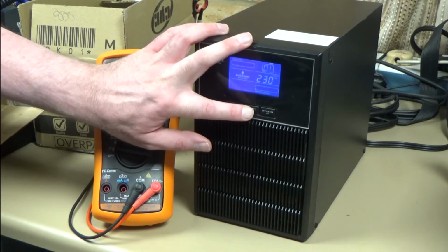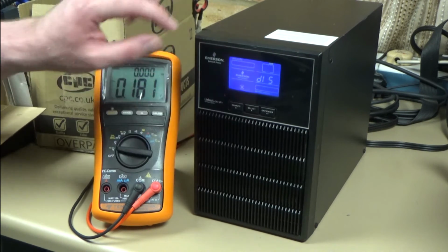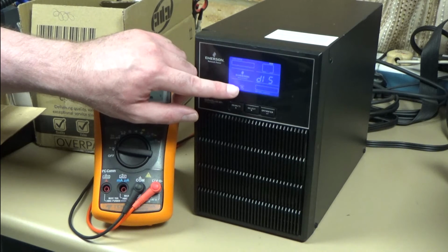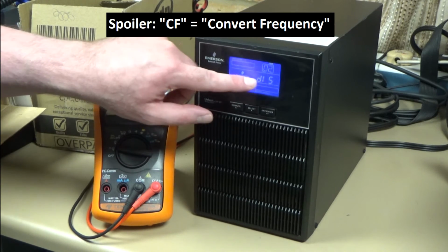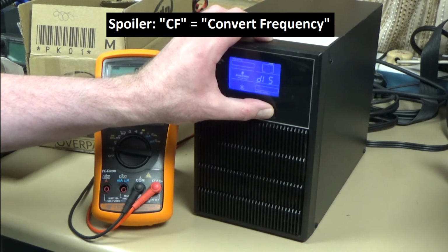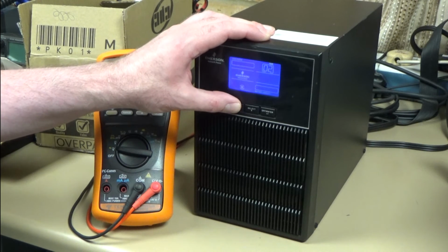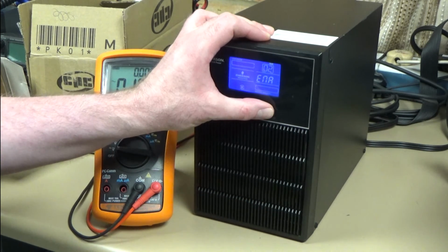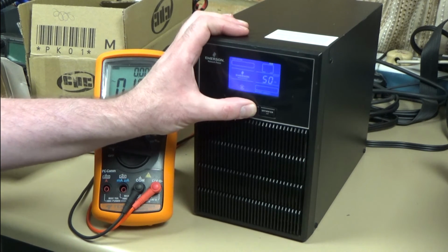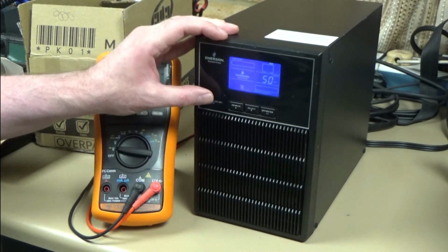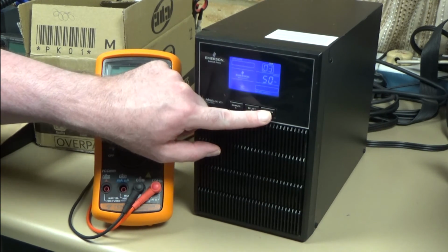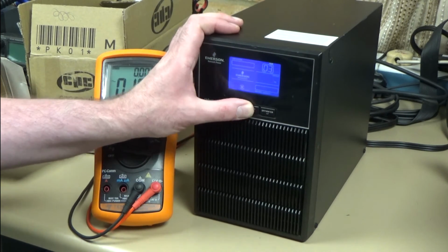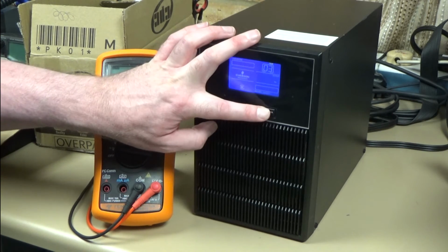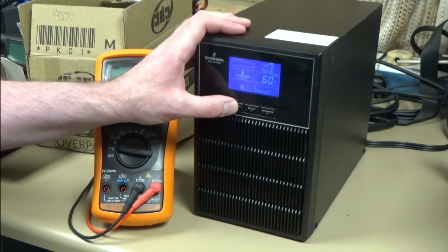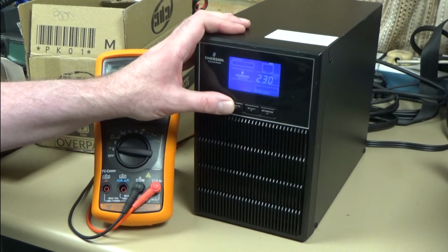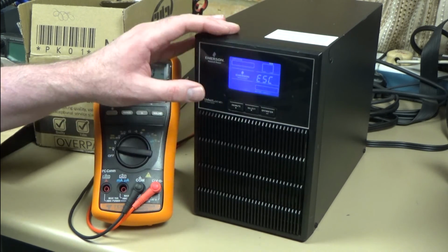But if we go through the menu options, we have this CF thing, which is currently DIS, meaning disabled. If we select that and enable it, so that is now enabled, if we carry on going through the menu options, we can set the output frequency. It's currently set to 50 Hertz. If we change that, we can change that to 60 Hertz. Lock that in, go back to 0, which is just to exit the menu.